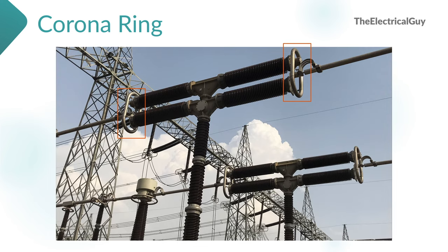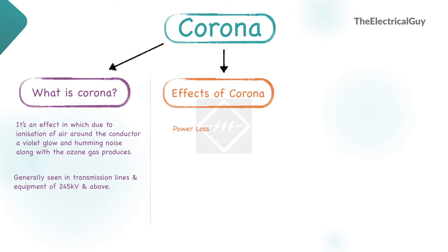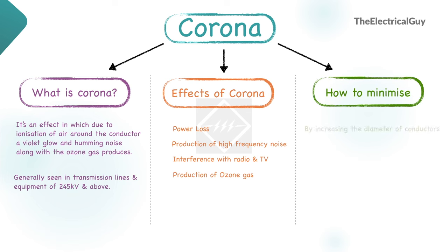So these are the ways to minimize the corona effect. Let's summarize: Corona is an effect in which, due to ionization of air around the conductor, a violet glow and humming noise along with ozone gas are produced. Corona is generally seen in transmission lines and equipment of 245kV and above. Corona can cause a lot of power loss and produces high-frequency noise which can interfere with nearby radio receivers and TV sets. Production of ozone gas can reduce the life of insulators and conductors. Corona can be minimized by increasing the diameter of the conductor or bundling conductors in sets of 2, 3, or 4 per phase; for high and extra high voltage equipment, corona rings can be used. You can take a screenshot of this summary slide, store it in your phone, share it with your friends, and read it whenever you want.